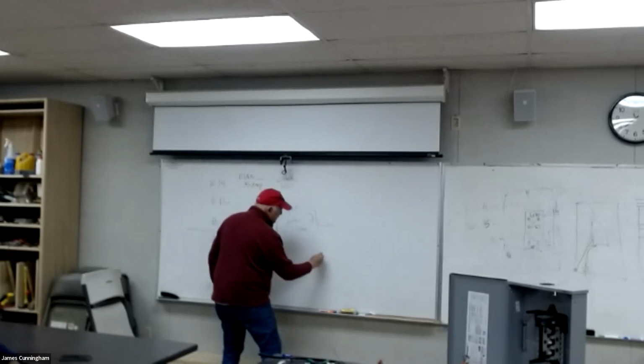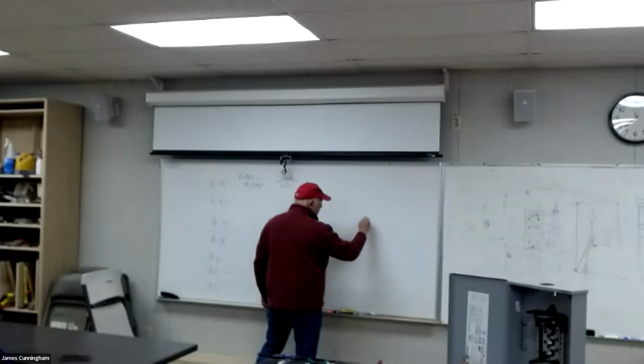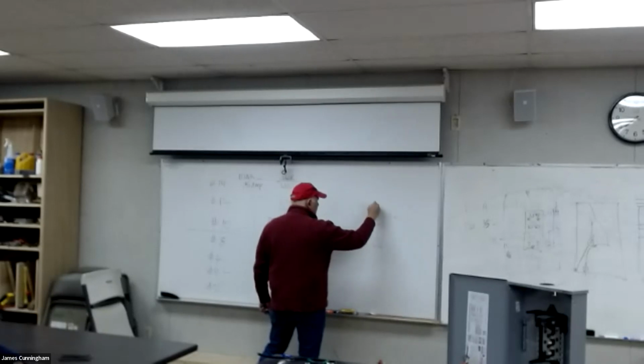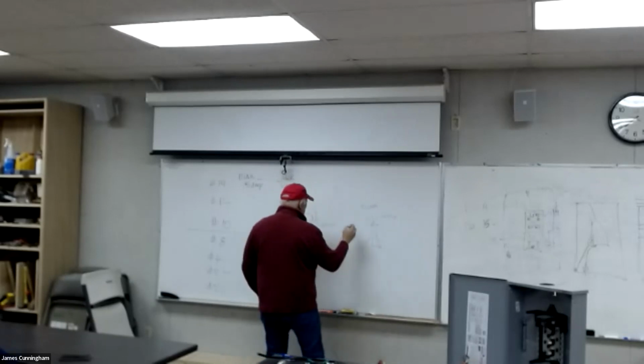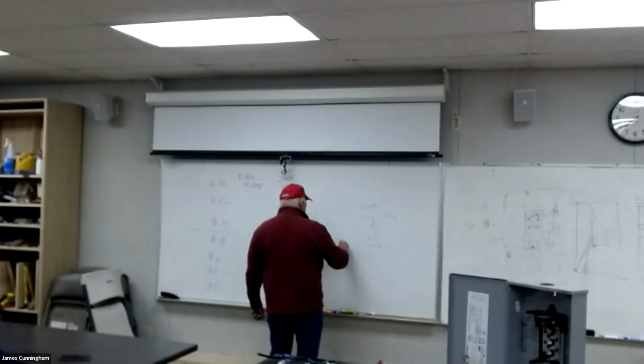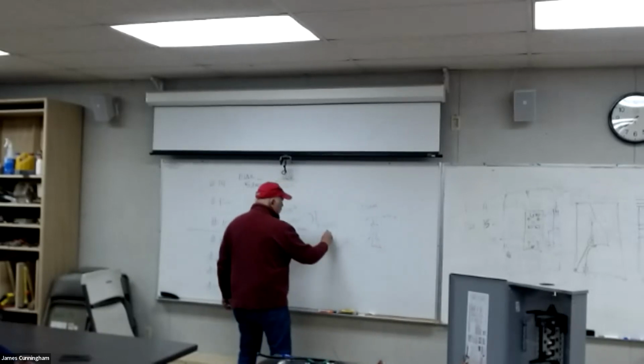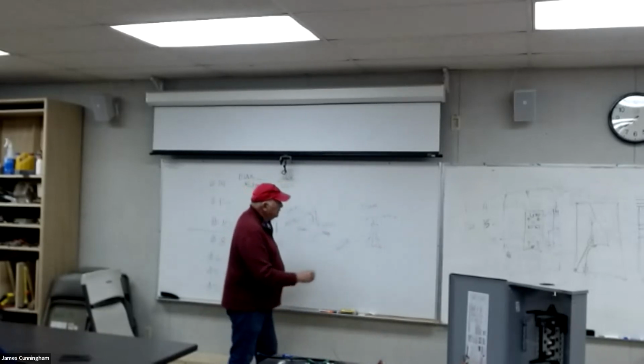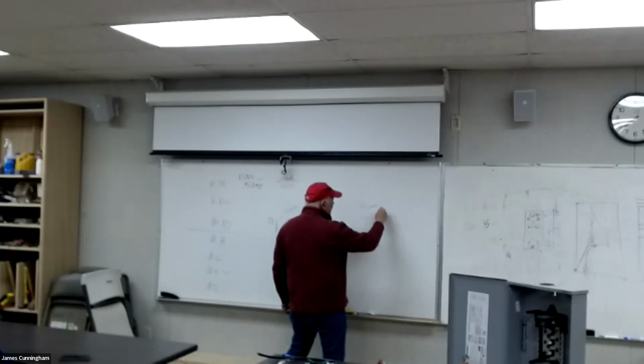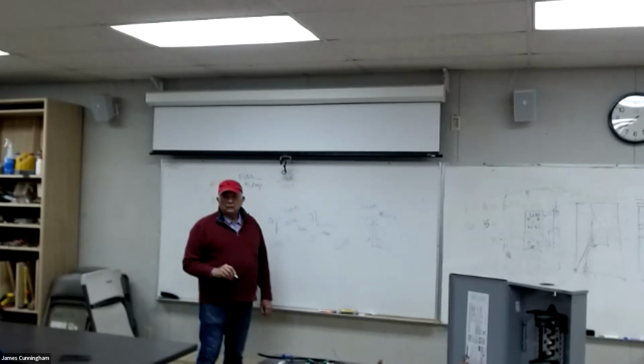And then I'm gonna have a Romex that comes here, and it's gonna go over here to a light fixture. And in my light fixture, I'm gonna have a bulb, with wires coming in like this. I'm gonna have a white wire and a black wire. My white wire is just going to get wire nutted together with this white wire. I'm gonna put a wire nut on it here, and wire nut those together, and then it's gonna go over here to my white wire, and I'm gonna wire nut it together there. The white wire just goes through.